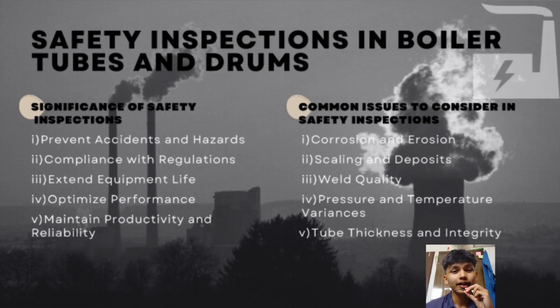The third significance of safety inspection is to extend equipment life. By identifying and addressing problems early on, safety inspections can help extend the operational life of boilers, tubes, and drums, reducing the frequency of repairs and replacements. Next is optimized performance. Regular inspections allow for the identification of inefficiencies and deviations in boiler operation, enabling adjustments to enhance performance, energy efficiency, and cost effectiveness. Okay, for the last, safety inspection helps maintain productivity and reliability. Properly maintained and inspected boiler tubes and drums ensure consistent and reliable operation, minimizing downtime and maximizing productivity.